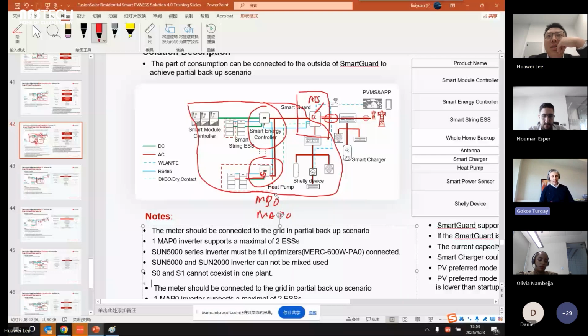So then it acts like a combiner box plus an automatic transfer switch, switching between grid and the PV side, or an off-grid system, under 20 milliseconds. Yes, 20 milliseconds, and we can connect 3 systems to the PV side.